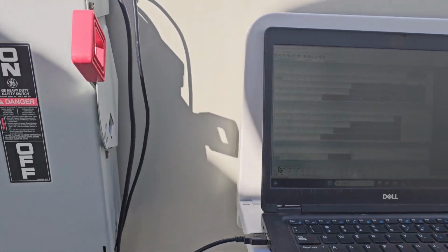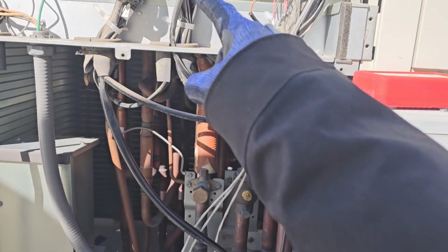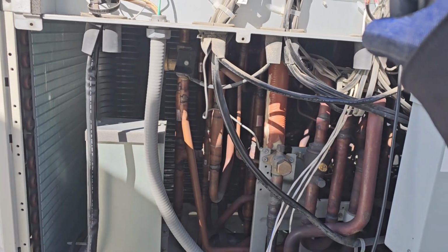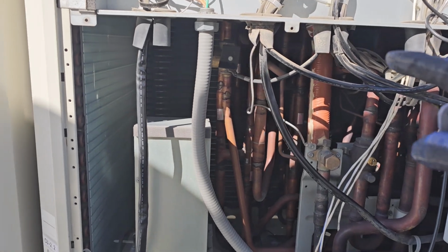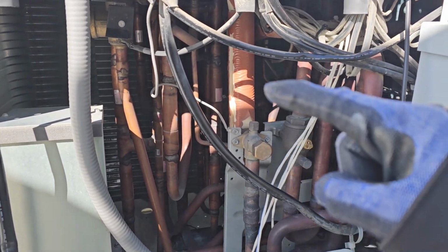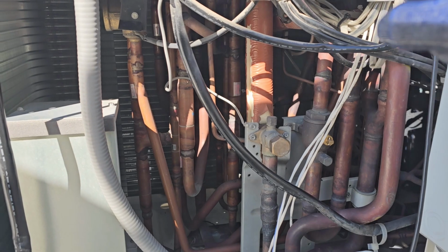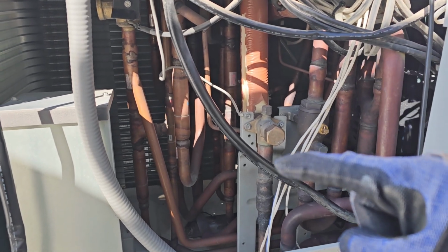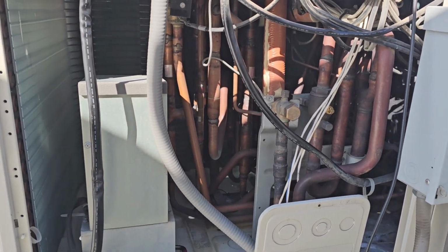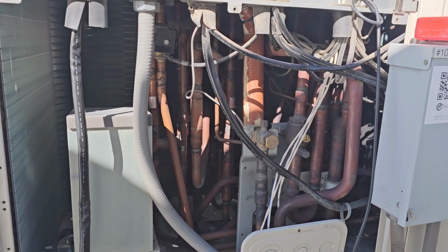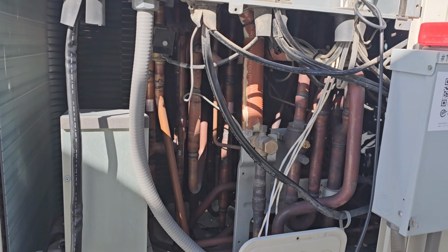I'm getting hot gas from my compressor to my four-way valves. Coming out of the four-way valves, it wasn't even that hot. It was pretty warm. And then coming down, and then as like before we entered the hot gas line, leaving the unit, it was just lukewarm. And I kept saying to myself the whole time, it's almost like it's not even flowing.